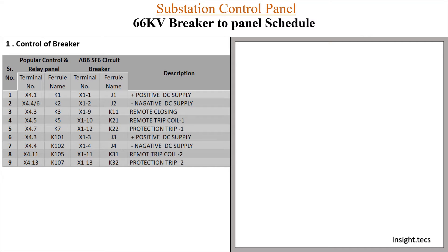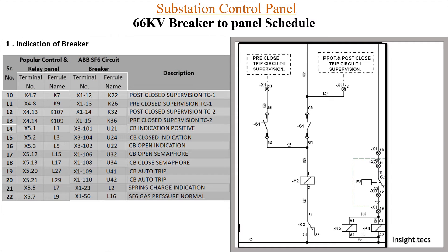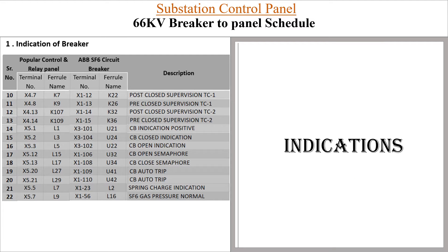For control of the breaker, we covered points one to nine. Basically, control means turning on and turning off of the circuit breaker, and what kinds of wirings are done for that. Second is the indication of the breaker: post close supervision, breaker open indication, breaker close indication, breaker close semaphore, and spring charge indication. These are the basic indications of operation of the breaker. Now let us continue in this section further.